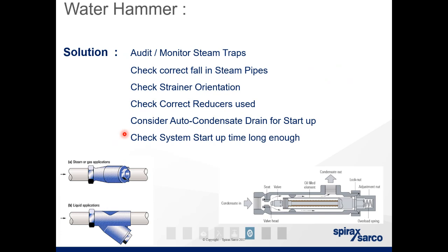Solutions we can cover here, as we've alluded before, are audits and monitoring of steam traps. Check the correct fall of steam pipes. As we were saying, the 1 in 100 drop allows condensate to run towards a trap. Check the strainer orientations so that you're not allowing a buildup of condensate. Reducers, as we covered before: look they're in the right location and the right ones are used. And auto condensate drain, which I'll cover in a second.